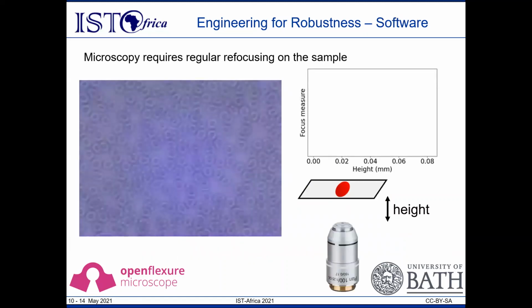The FMEA and considerations of failure modes isn't just for the hardware, it also applies to the software that we include with the microscope. On a manual microscope, hardware and sample imperfections as you travel around the sample mean that the system can easily lose focus. A microscopist can fix this by regularly moving the optics up and down to find the focal point where the image is sharpest.